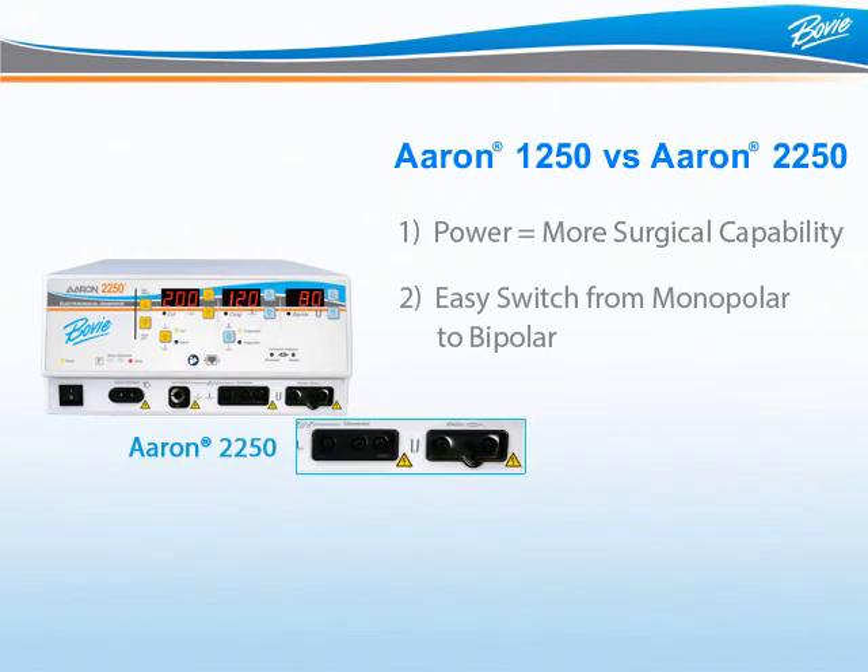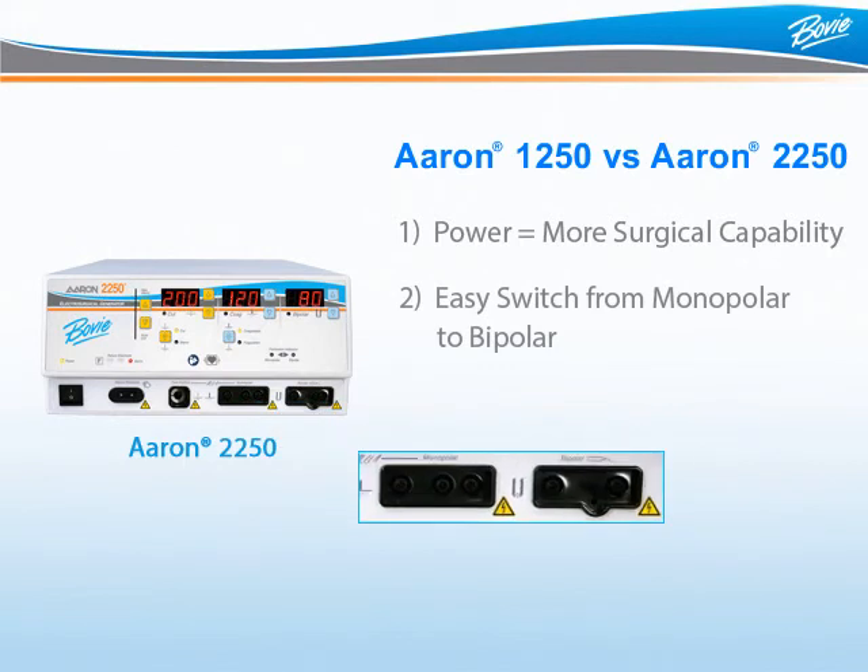What is the difference between the Aaron 1250 and Aaron 2250 besides power? First, more power provides more surgical capabilities — with 200 watts, it allows the surgeon to operate in areas of higher tissue impedance. Second, the Aaron 2250 allows the user to move from monopolar to bipolar without returning to the unit; the surgeon simply picks up the device and activates. On the Aaron 1250, the surgeon or nurse must switch from monopolar to bipolar on the generator. This convenience factor is a big deal for many surgeons and an important selling point.